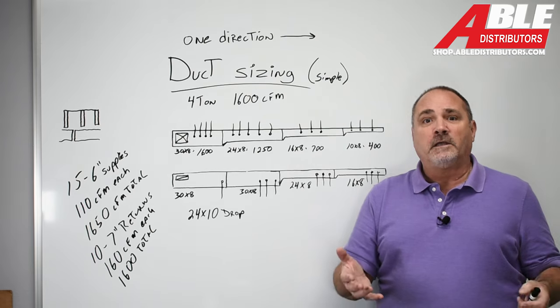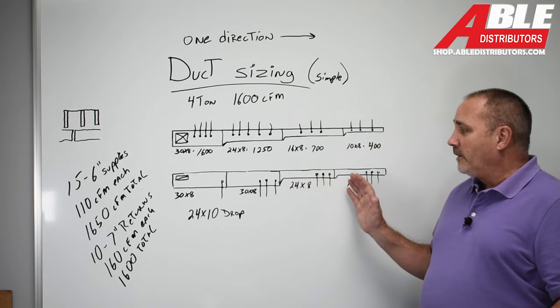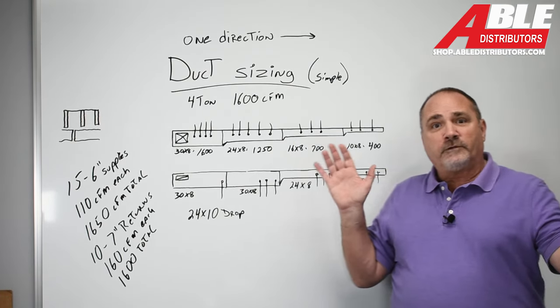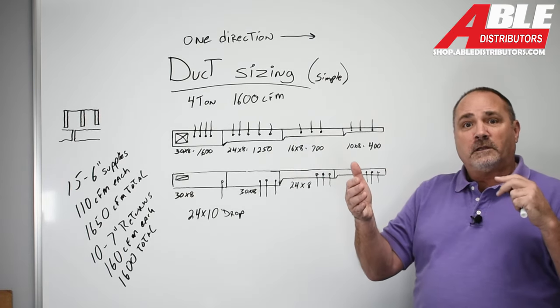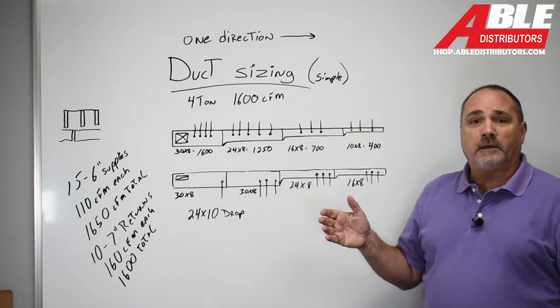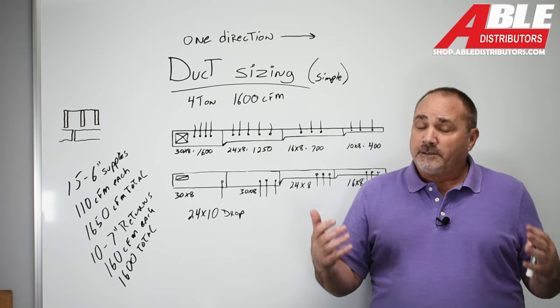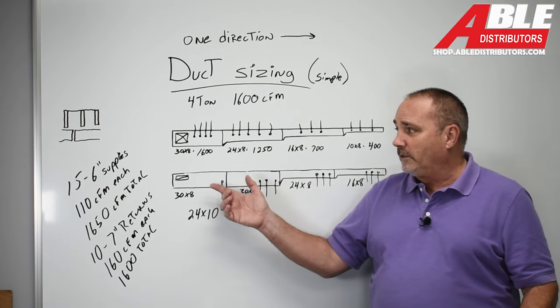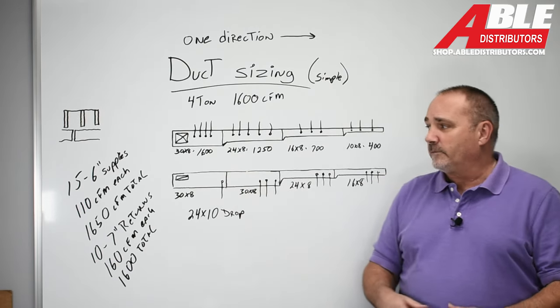So the two trunk lines don't match perfectly, and they're not really designed to match perfectly. Sometimes they might, but more often than not, you're going to find that the bulk of your returns are in from the outside walls, in the middle of the house. So usually your return trunk line ends up to be shorter. It doesn't mean that it can be smaller. You still have to be able to have the capability of a full 1600 CFMs.